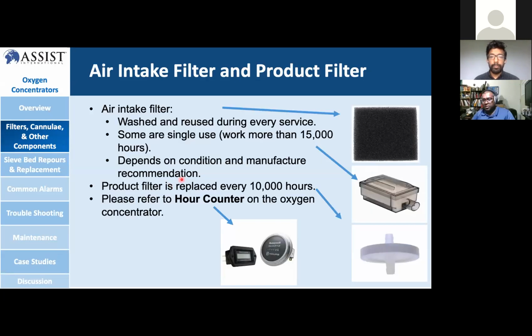So we did talk earlier about filters. Air intake filters come in a few types. One is the washing type that you can wash and reuse again. And some are single use that work for 15,000 hours, then eventually you have to replace them. You cannot clean them, though some you can clean. Depending on the condition and the manufacturer's recommendation, you have to replace accordingly. Yes, it may work more than 15,000 hours, but sometimes you end up replacing at maybe 10,000 hours because that area may be dusty or something like that. So eventually your filter needs to be replaced.